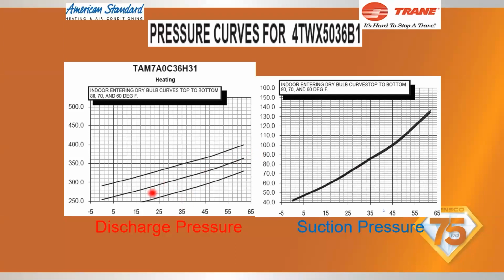So you have our discharge pressures. Again, this is on a single stage 15 SEER 3-ton. We have our 80, 70, and 60 lines. 80, 70 degrees indoor, 60 degrees. And then our suction pressure has our single line. Well, this one's a little bit better illustration. You can see all 3 lines, but they're just so close that it's just using one.